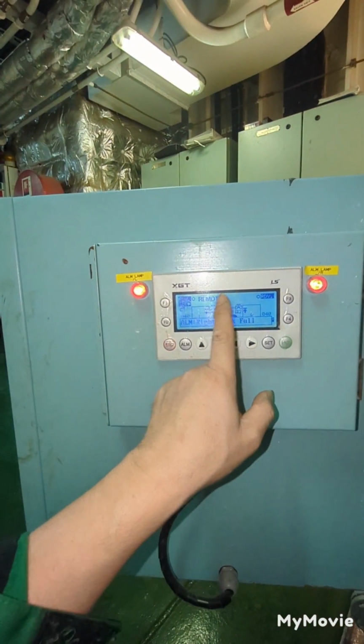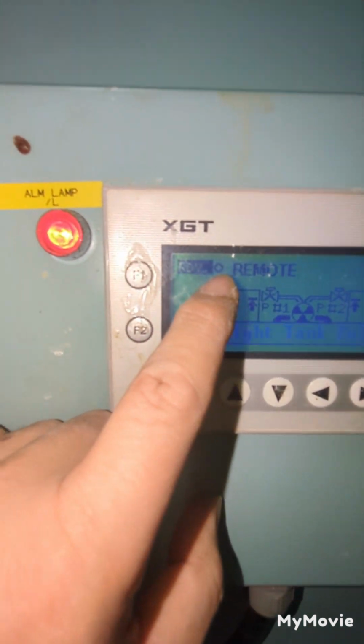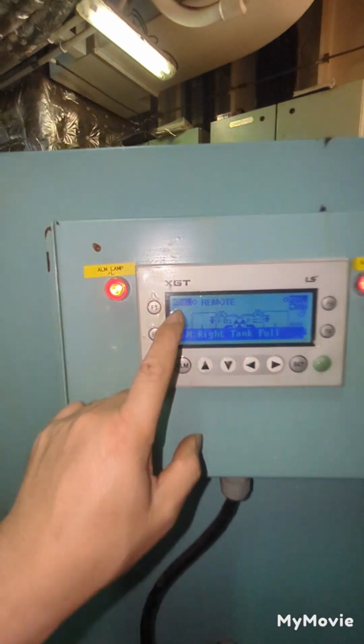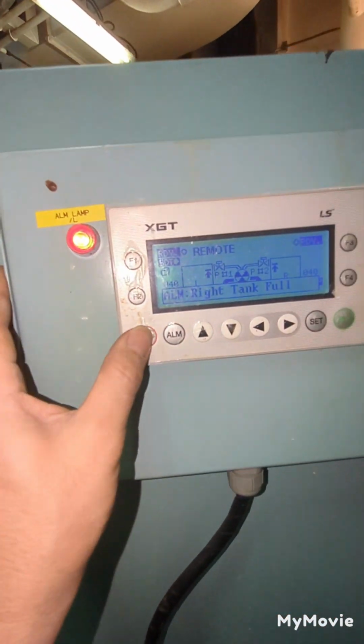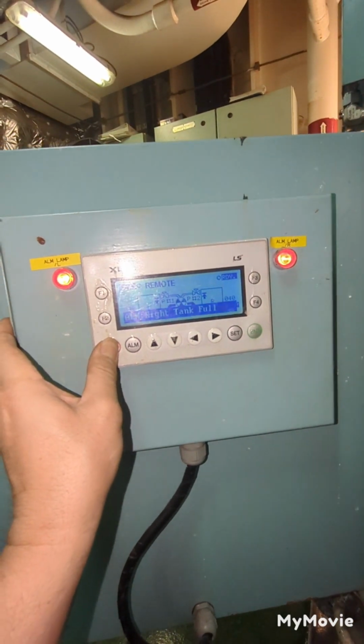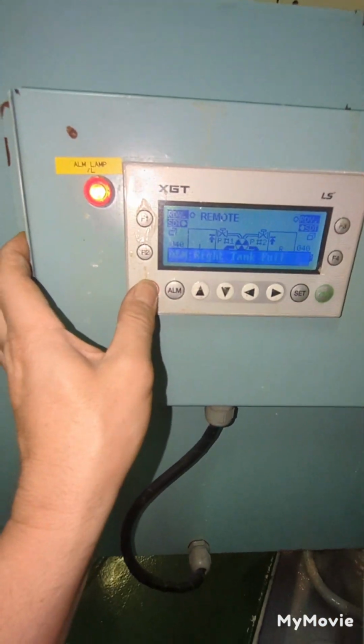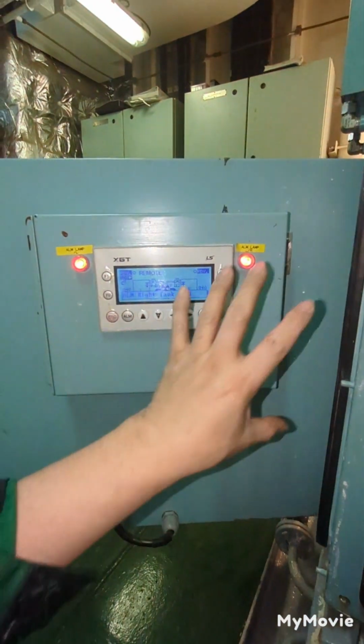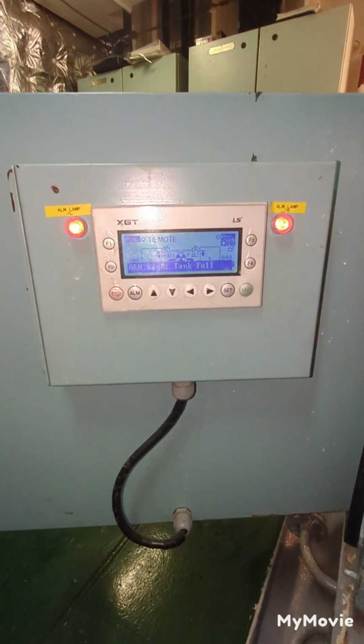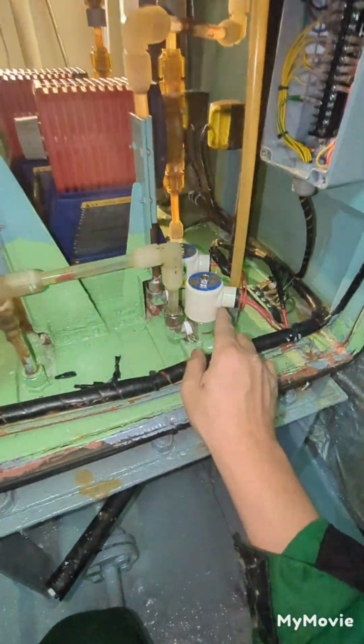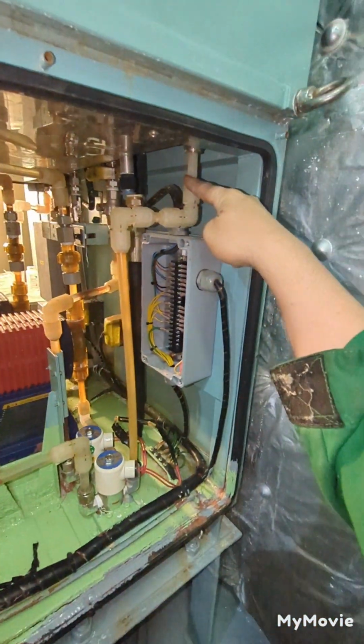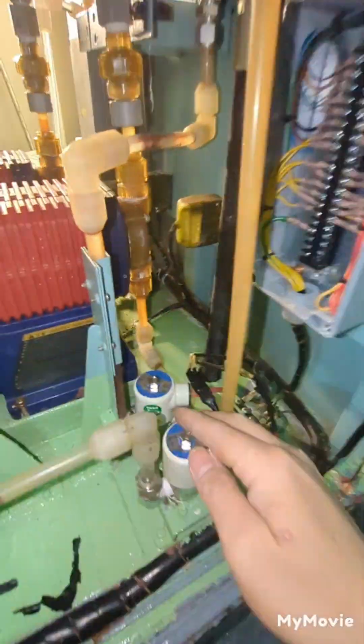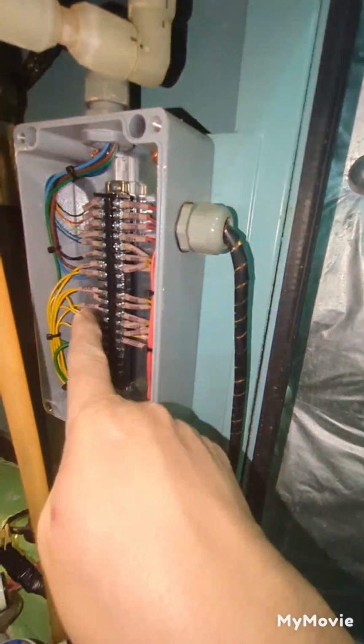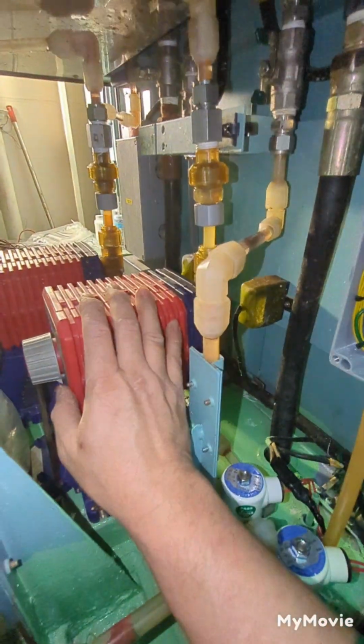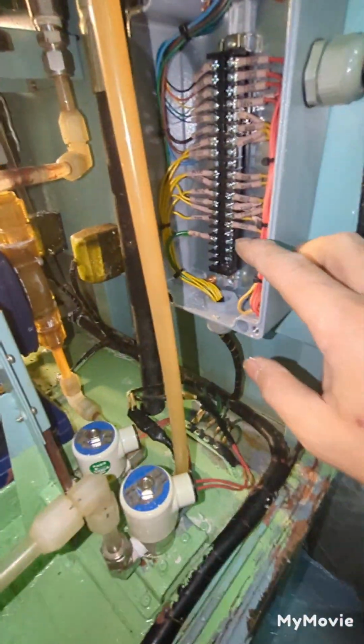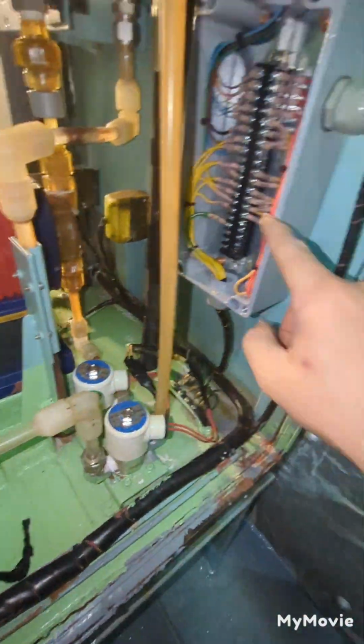So in order for me to make it ready, this color must be darkened for remote and become ready. But before it becomes ready, I need to press escape here. You see? But here, the escape button is not working. So in this case, it is not possible for us to use those output devices to fill water in our tank. The output devices to operate this solenoid valve get their signal from R006, and the dosing pump gets its signal from R0012, this one.